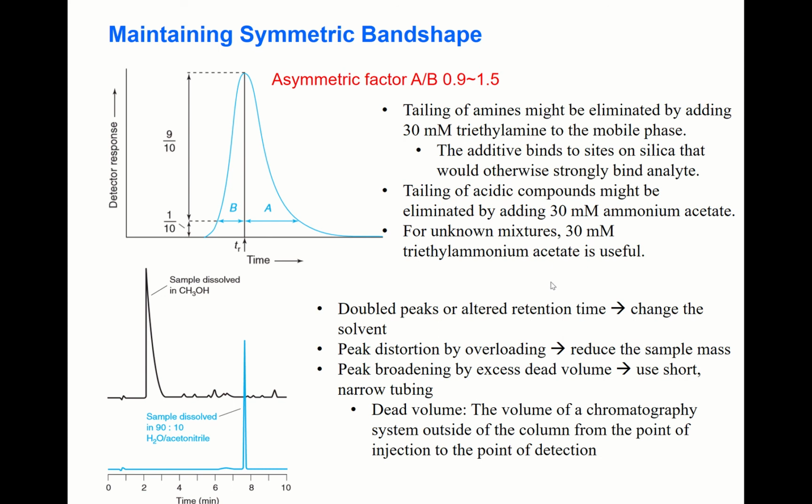So if you don't know the components but you observe this kind of tailing, you add 30 millimolar triethylammonium acetate. That's the idea.